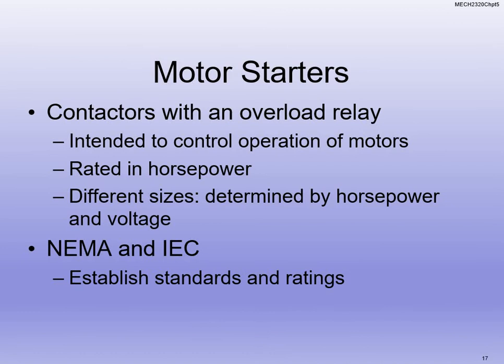Motor starters are very important. We use a PLC to start a motor via contactors — the PLC is low voltage at 24 volts, while your motor is 480-volt, 3-phase, really high current. We use motor starters for that: it's really just a relay contactor. The PLC sends a control signal, current goes through the wire, the wire creates the magnetic field in a solenoid-type scenario, and it closes the contactors so the motor starts. We have to make sure we size the motor starters to their rated horsepower, and wire size must match the current that motor will draw. All of those guidelines are in the National Electric Code.